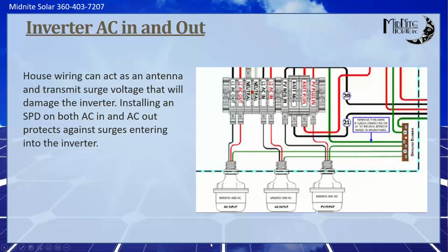Something that I want to point out is AC ins and AC outs. Any input or any connection to an inverter, let's say. Again, I've had a customer who had an off-grid system smacked by lightning, and he's like, well, the only thing going to the input's a generator, and it's 50 feet away. I figured it was safe, and that came into the input. So if there's any wire hooked to it, I highly suggest putting a surge arrestor on there if you're in a lightning prone area. It's one of those areas where it's a little bit of money up front, but when things go wrong, it's a lot of money on the backside and or insurance claims or however you handle that. So it's pretty cheap insurance to protect all of those inputs and outputs of expensive equipment.